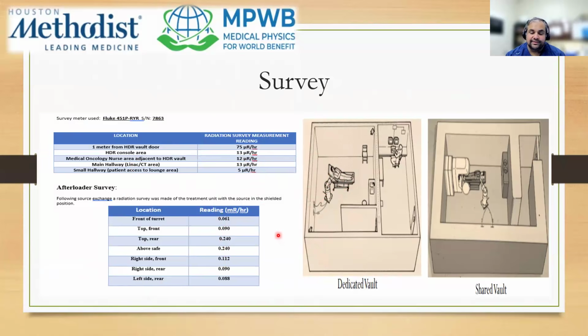Recently, there was an incident in one of the clinics where after treatment, they got an error notification, but for some reason they were able to clear it. Only when the physicist walked in and brought the survey meter near the turret did they see that the numbers were going quite high. What happened was the source went back toward the safe, but not all the way back. There was still a source outside the safe, and that's something no one expected.